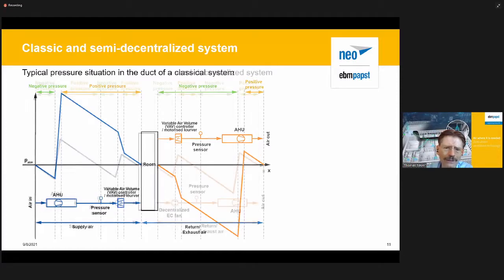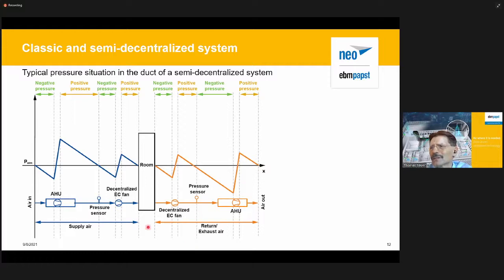So how does that look in a semi-decentralized system? As we do have the capability of this decentralized fan to suck in air from the channel, we can allow the channel pressure to go to zero. A typical setup could be that we use a pressure sensor at a point in the duct where we would like to have the pressure at 0. What we really do is that the pressure at that point is around, say, 10 pascals, something in that range. Obviously, due to the friction in the system, we will not get a steady pressure throughout the ducts. But I think you get the difference in what happens to the air power that we would need to supply into the system.